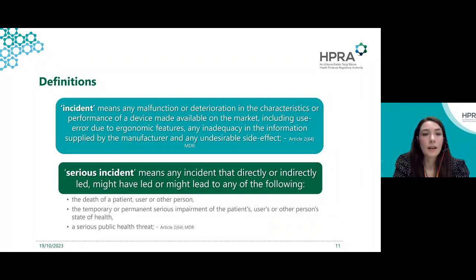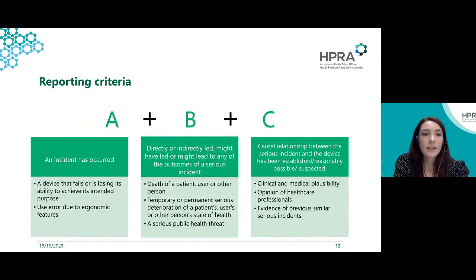So I'll just explain more about reporting criteria. The ABC criteria are useful when considering if a particular incident is a serious incident. So first, under A, an incident has occurred. That is, something has happened where the device has not worked as it should, or it did not meet the expected performance. An example under A could be a device breaks during use, although it was handled correctly in accordance with the instructions for use.